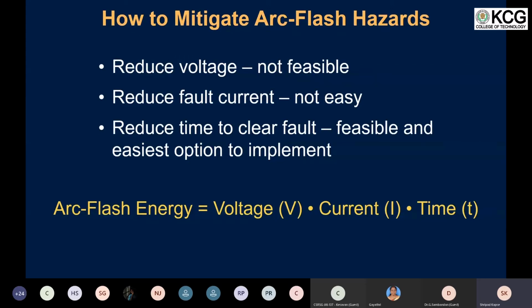Now let us look at ways to reduce the arc flash energy, in order to minimize the harm it causes to personnel standing right next to the switchgears, and the damage it can cause to the equipment. This energy is proportional to the voltage multiplied by the current and multiplied by the time. Here the voltage is the operating voltage of the system. It could be a 415 volt system, or a 3.3, 6.6, 11 kV or a 33 kV system. In these cases, reducing the voltage is not a very feasible option.